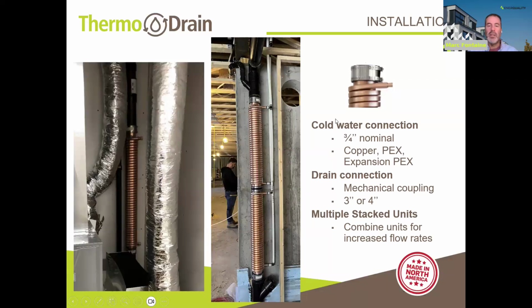And here you have, in a house standard drain stack, a unit installed, ready to get the cold lines hooked up. These devices come with any kind of a connection you want on it, PEX or copper or expansion PEX. So it's an easy install with the no-hub drain couplings. Basically the installer doesn't really need to supply anything for the installation of the drainwater heat recovery unit. He starts with his lines.